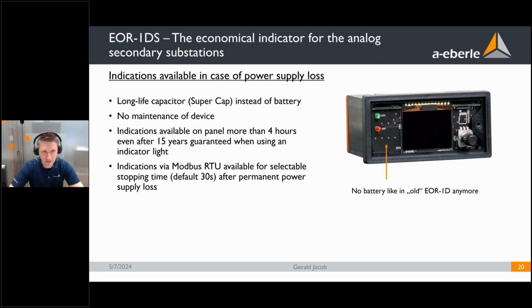And one remark regarding the Modbus RTU interface. In case of such a power supply interruption, the Modbus RTU interface will send you the latest data for, for example, 30 seconds, and then will quit the indication, and it will automatically recover the Modbus RTU as soon as supply voltage is available again.